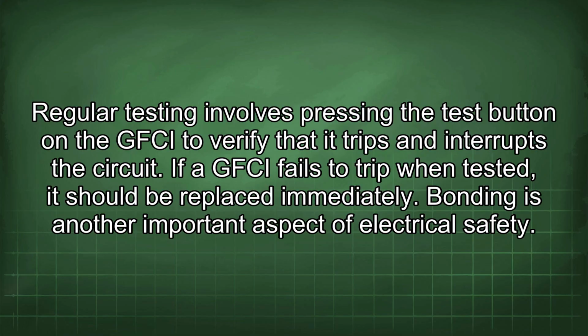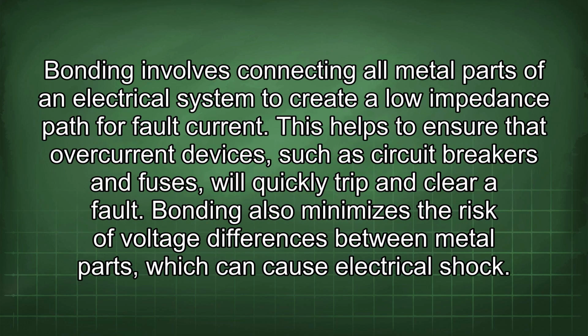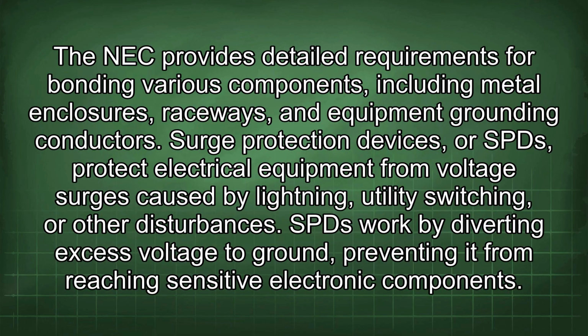Bonding is another important aspect of electrical safety. Bonding involves connecting all metal parts of an electrical system to create a low impedance path for fault current. This helps to ensure that overcurrent devices, such as circuit breakers and fuses, will quickly trip and clear the fault. Bonding also minimizes the risk of voltage differences between metal parts, which can cause electrical shock. The NEC provides detailed requirements for bonding various components, including metal enclosures, raceways, and equipment grounding conductors.